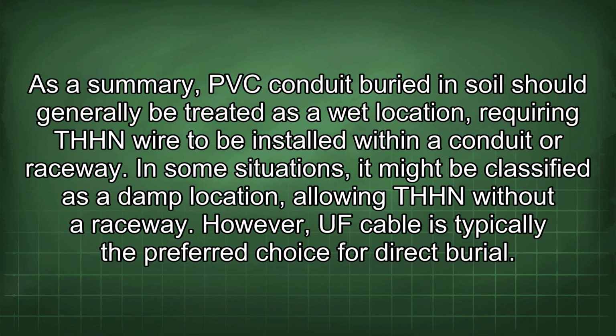As a summary, PVC conduit buried in soil should generally be treated as a wet location, requiring THHN wire to be installed within a conduit or raceway. In some situations, it might be classified as a damp location, allowing THHN without a raceway. However, UF cable is typically the preferred choice for direct burial.